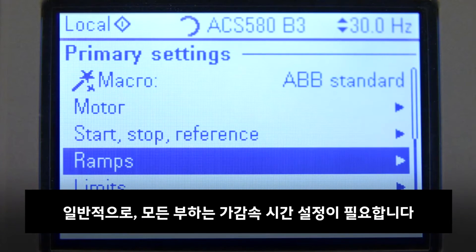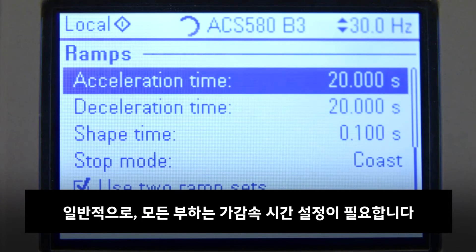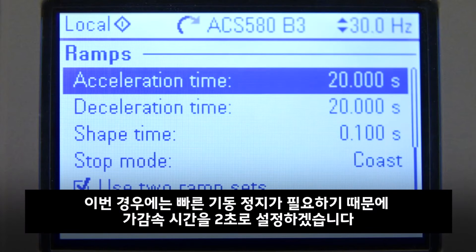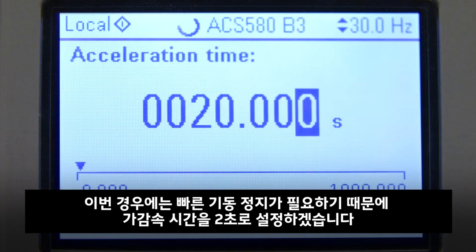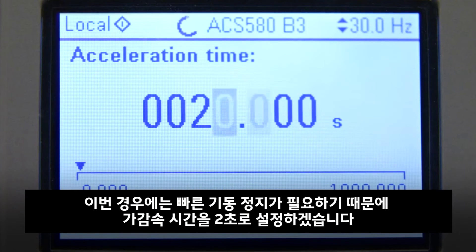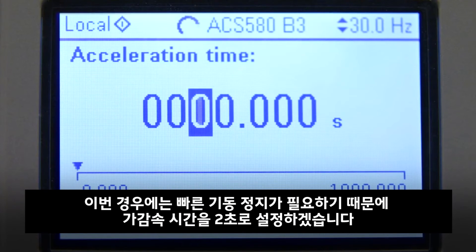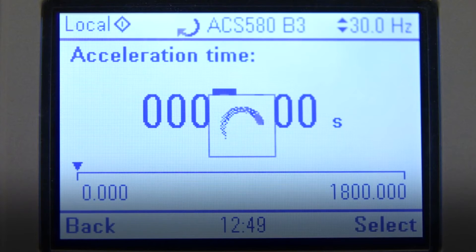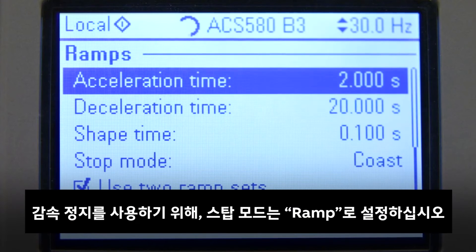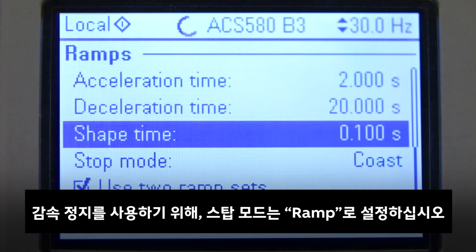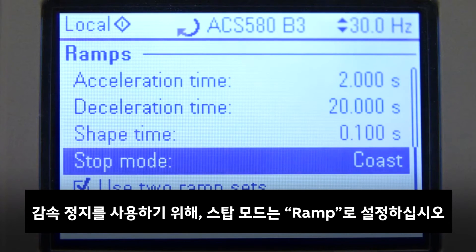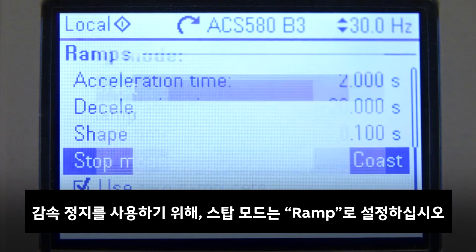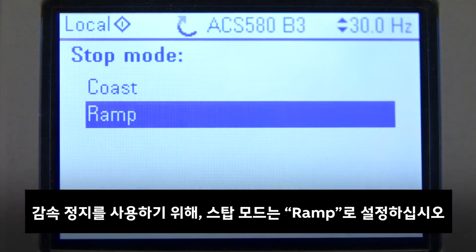Typically, we need to adjust the ramp times in every application. Here we need a short ramp time, so we will set the time to 2 seconds for Start and Stop. Stop mode has to be changed to Ramp Stop to use the deceleration ramp.